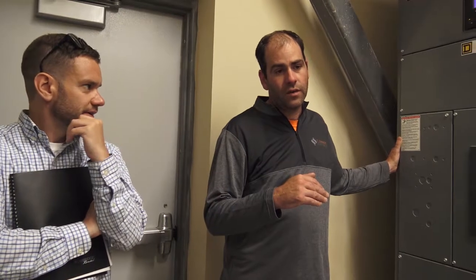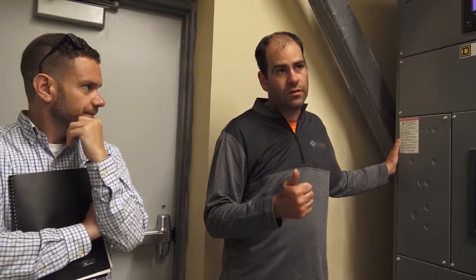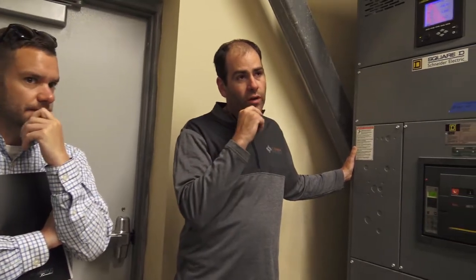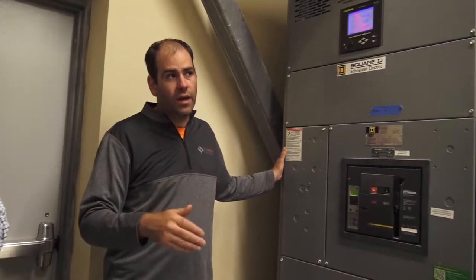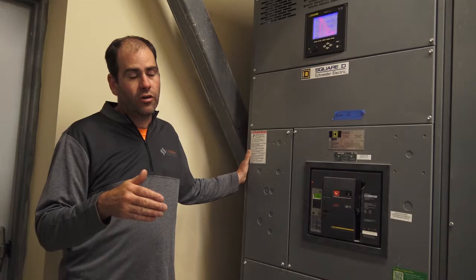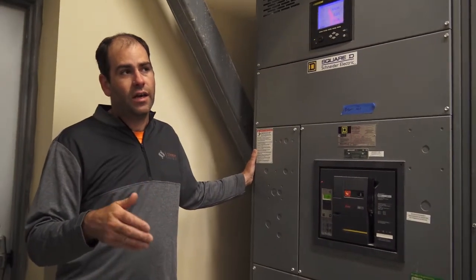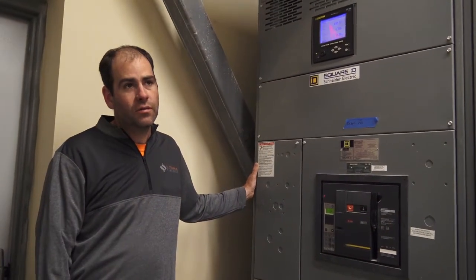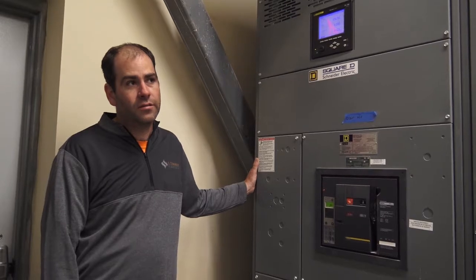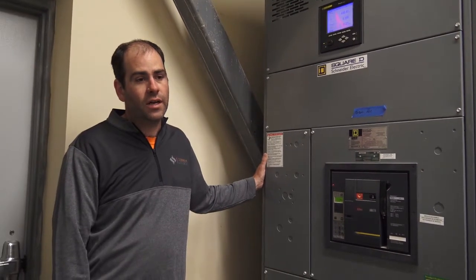You would take the equipment branch down first, and I'll show you in the next panel where those breakers can be fed from. Then we'll go down to critical branch, which would come down second, and the life safety should never really be shut off. That's going to be your last load you're going to keep on.